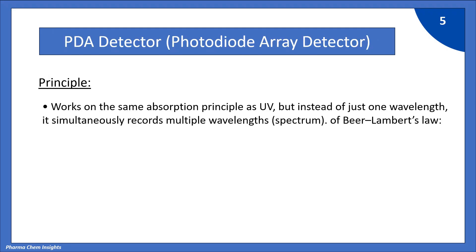Now let's see the principle of the PDA detector — that is, the photodiode array detector. It works on the same absorption principle as UV, but instead of just one wavelength, it simultaneously records multiple wavelengths, capturing a full spectrum.